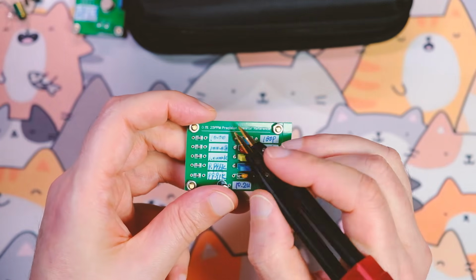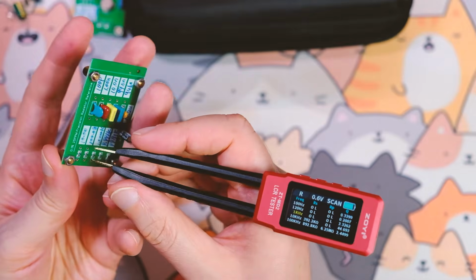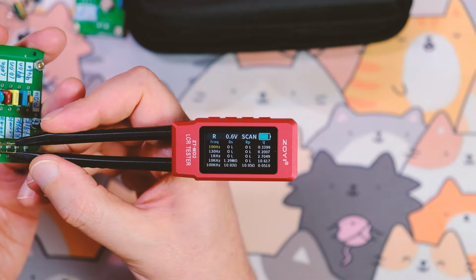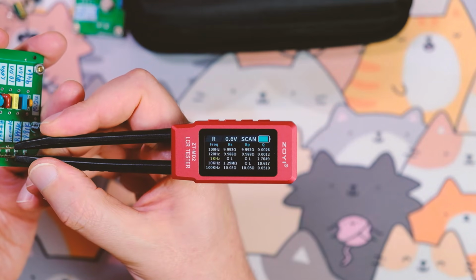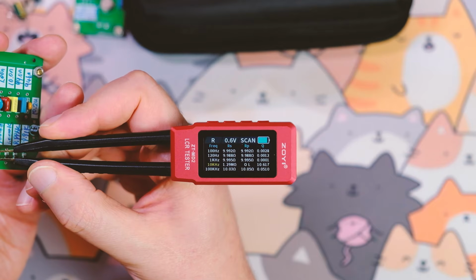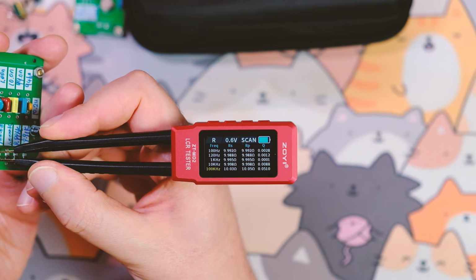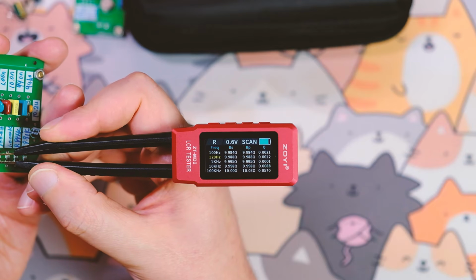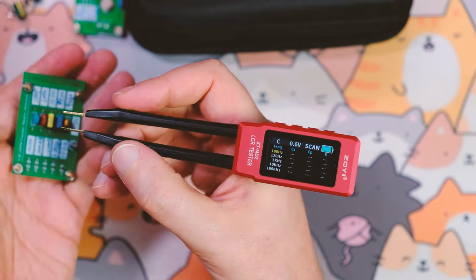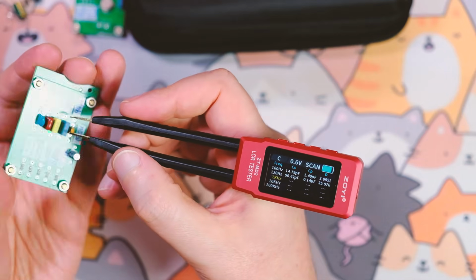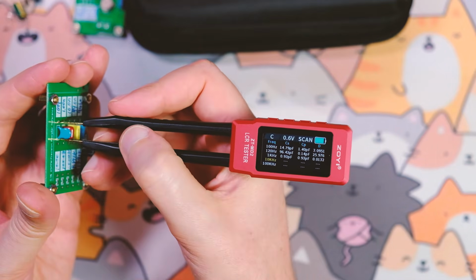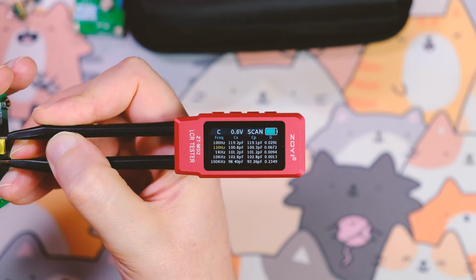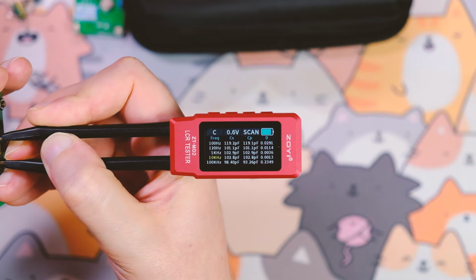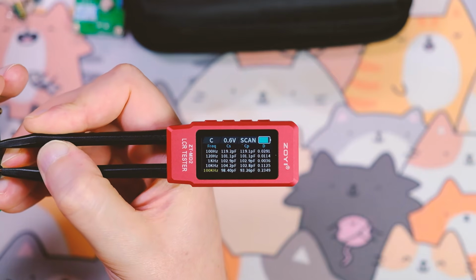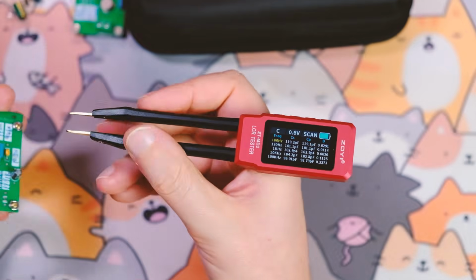Now I'll try to measure a 10 ohm resistor at 100 Hz, 120, 1 kHz, 10 kHz, and 100 kHz. In principle, there's no point in measuring resistance in scanning mode, but there is a point in measuring capacitance in this mode. We will measure a 100 picofarads capacitor. When scanning capacitance, the second parameter scanned will be the dissipation factor. Unfortunately, in this mode, the second parameter cannot be selected.